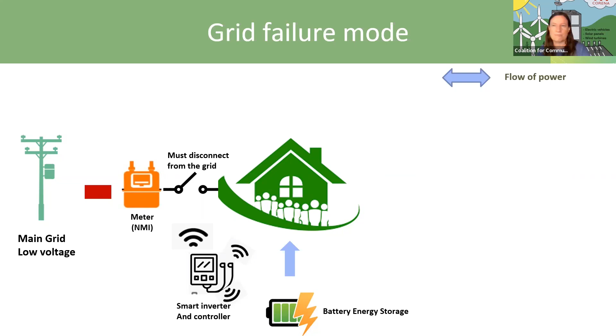With the smartest systems these days, you might not even know you've had an outage, because your power stays on without even a flicker. One big issue is sizing your battery or backup generator, or a combination of both, so you know how long your outage might last and how to size your microgrid accordingly. You might have a small generator and a large battery, or vice versa.